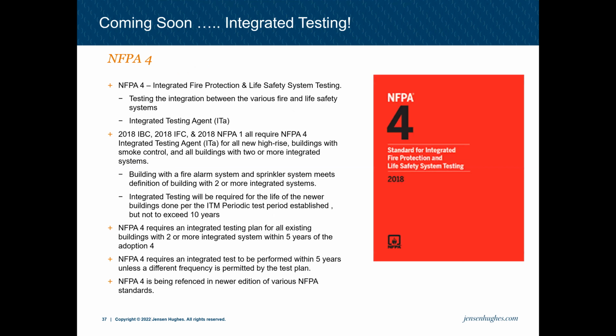This is kind of the last technical slide, which isn't exactly related to smoke control, but something we do want to bring up: 780 CMR 10th edition. I'm not sure when the new fire code will be adopted, but the newer codes, so 2018 IBC or 2021 IBC, will be adopted through 780 CMR 10th edition. And whenever the fire code becomes updated and adopts a newer edition of NFPA 1, those will require integrated testing of fire protection and life safety systems.